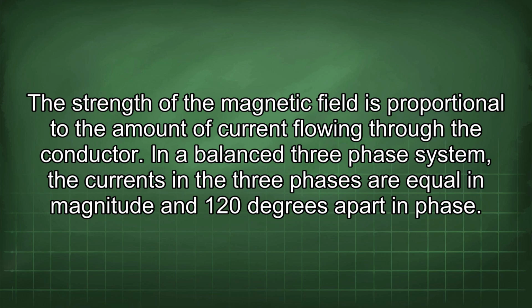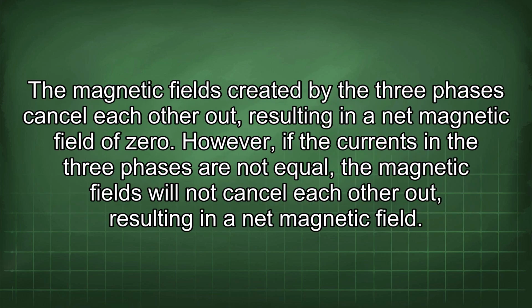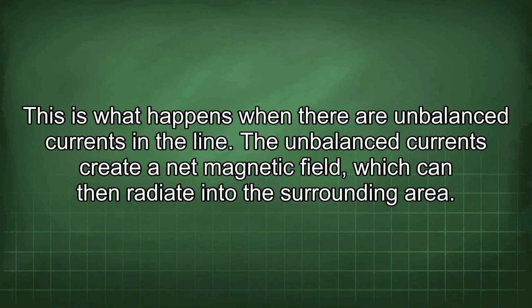In a balanced three-phase system, the currents in the three phases are equal in magnitude and 120 degrees apart in phase. The magnetic fields created by the three phases cancel each other out, resulting in a net magnetic field of zero. However, if the currents in the three phases are not equal, the magnetic fields will not cancel each other out, resulting in a net magnetic field. This is what happens when there are unbalanced currents in the line. The unbalanced currents create a net magnetic field, which can then radiate into the surrounding area.